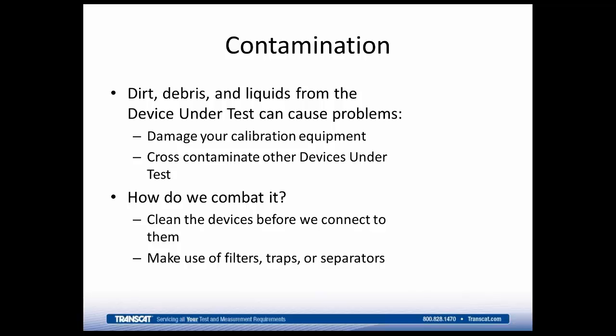How do we combat it? Clean the devices before we connect to them, make use of filters, traps, or separators, have separate pressure lines and fittings for different types of fluids so that you have one set that's used with oil and another set that's just used with air, so that way you don't get oil into your air systems.